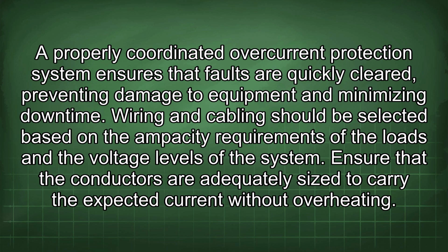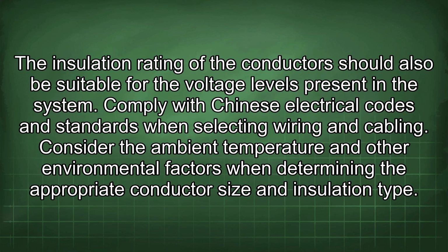Wiring and cabling should be selected based on the ampacity requirements of the loads and the voltage levels of the system. Ensure that the conductors are adequately sized to carry the expected current without overheating. The insulation rating of the conductors should also be suitable for the voltage levels present in the system. Comply with Chinese electrical codes and standards when selecting wiring and cabling. Consider the ambient temperature and other environmental factors when determining the appropriate conductor size and insulation type.